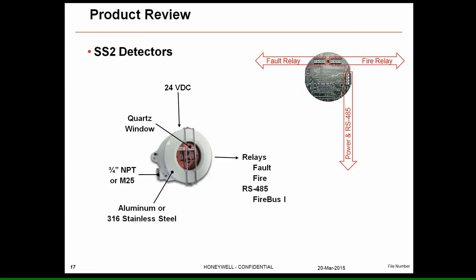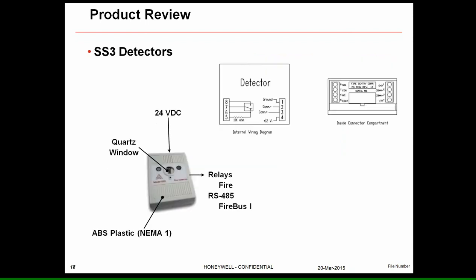The SS2 is the older generation — our first explosion-proof offering for the oil and gas industry. It uses a quartz window for UV, operates on 24V DC, and is available in aluminum or stainless with 3/4 NPT or M25 conduit entries. It has one SPDT fault relay and one SPDT fire relay, and uses the Firebus 1 protocol. There are only 12 connection points on this device, and there is no through-the-window optical self-test or switch-selectable options as found on the FSX series.